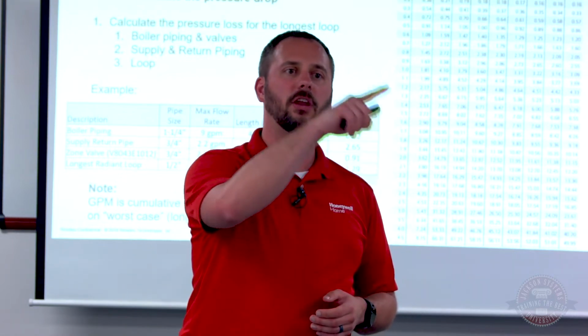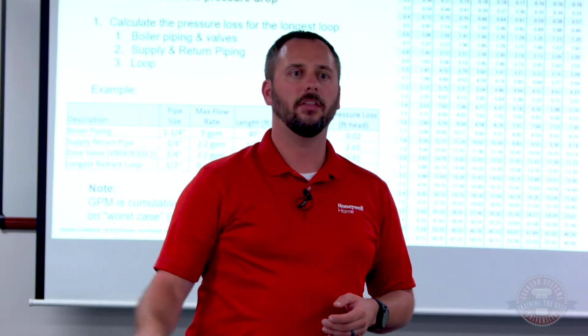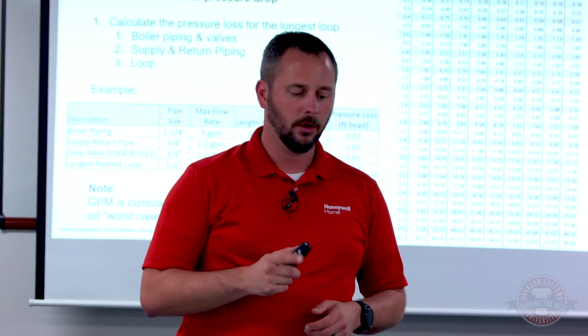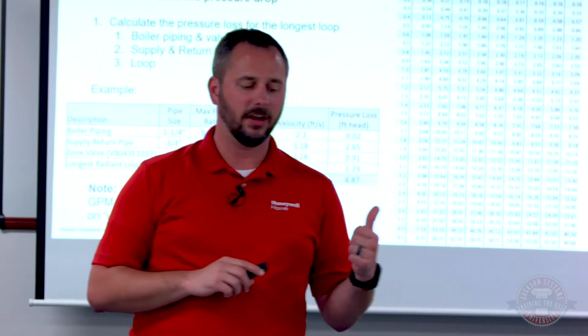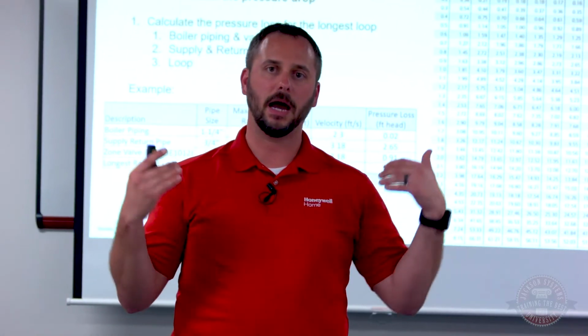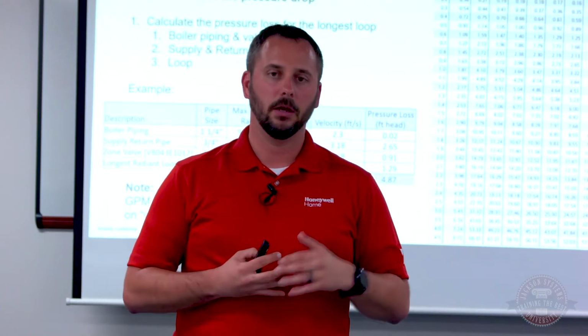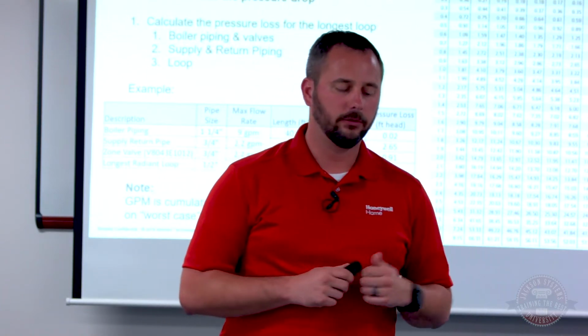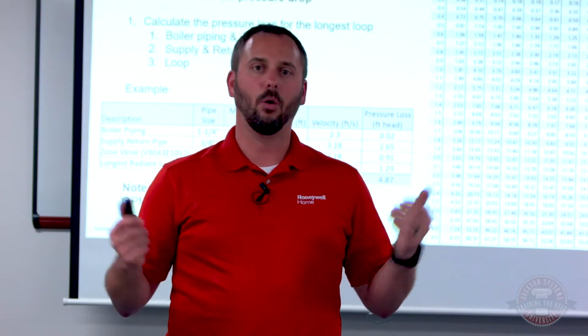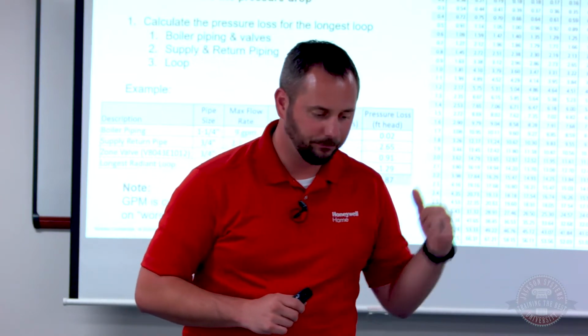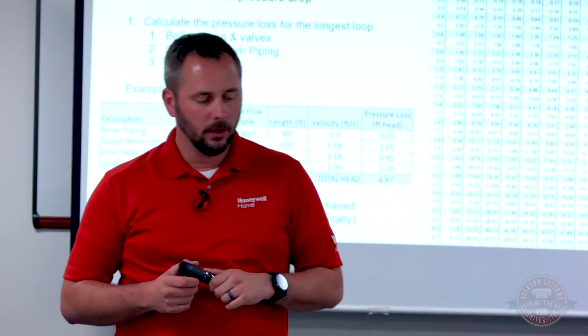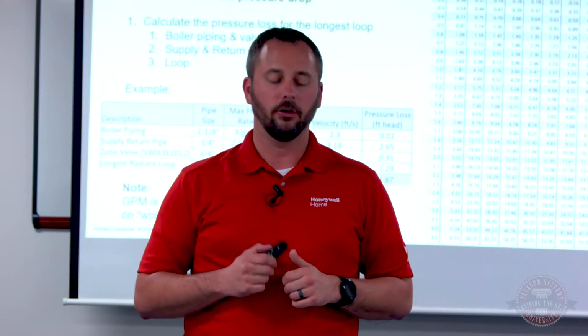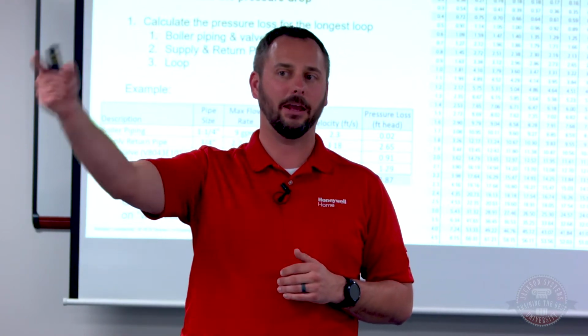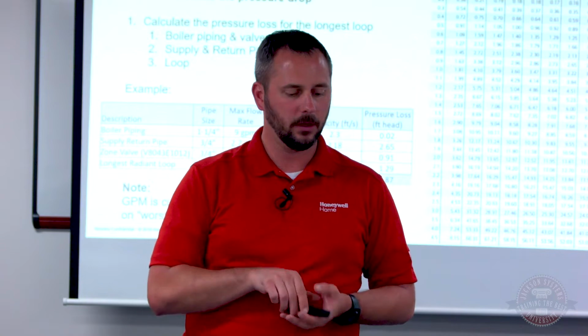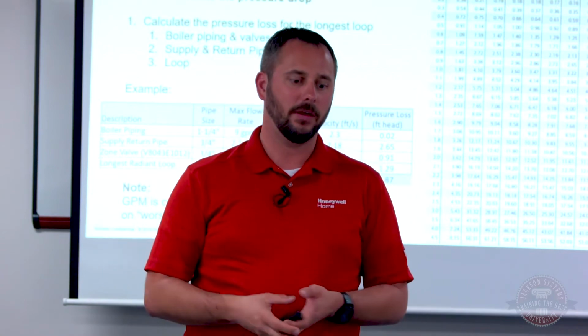So we're basically tracing everywhere that water's going and the pressure loss through every segment of it. In this example, I kind of totalized everything and put some examples of footages of pipe and distances of pipe and added up all of our head loss. So in the boiler piping, 1.25 inch, 0.02 feet of head. Supply and return piping, so 3/4 inch running 120 feet. That's supply and return because the water has to get back to you. We're looking at 2.65 feet of head.